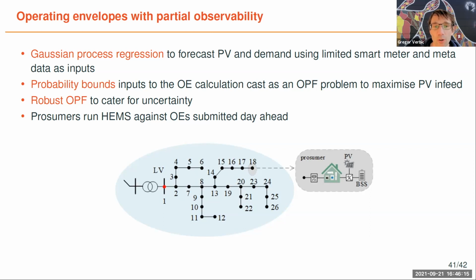The result of the Gaussian process regression gives you point estimates and also probability bounds, so you can see how much the demand can vary in real time when you do this forecast a day in advance, for example. Those probability bounds then serve as input into the computation of operating envelopes, which is formulated as a robust optimal power flow problem to cater for the uncertainty. Once you get those operating envelopes, you send them back to prosumers, and they can optimize or run their home energy management system against that.